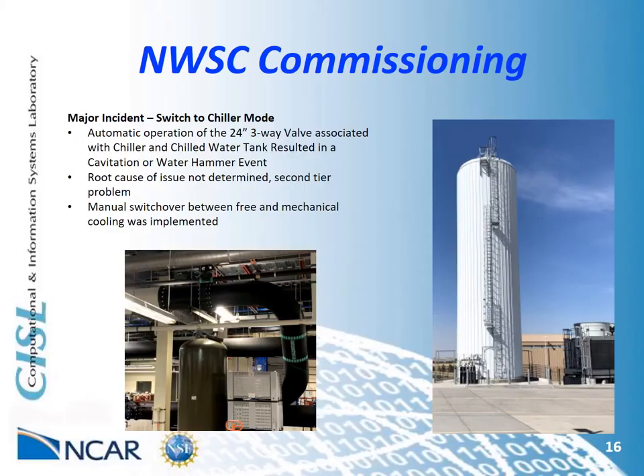During commissioning of the system, a major incident occurred within the chilled water piping. A control loop driven change in the three-way valve position that allowed flow through the reserve chilled water tank caused a significant event that could have either been cavitation or water hammer. This event was felt through the entire facility, and staff determined that some parts of the piping system physically displaced as much as 6 inches.